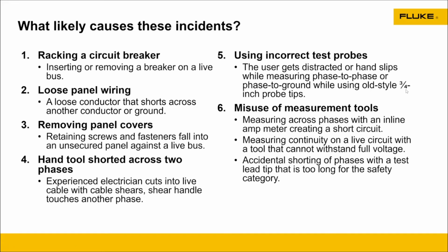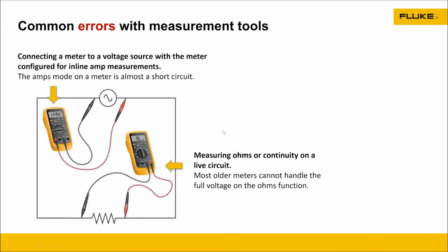Even using incorrect test probes. That first picture I showed you had a lot of exposed metal. It allowed that potential energy to run across the two of them and cause that arc fault, cause that arc blast. And then even sometimes the tools themselves, like a measuring tool like a DMM, if you're not using the correct meter for the environment, that could potentially also cause that fault and that blast to happen.